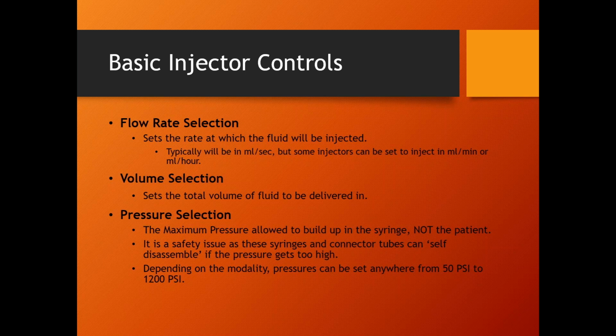CT, not as much as MRI, but CT is also a slower, longer procedure. So same exact reason. CT injections also only go up to 10 milliliters per second. So that's also why their pressure limits only go up to 300 PSI. Lower flow rates, lower pressures. So that was flow rate. I talked about volume selection, and then volume selection could be anywhere from 10 to 200. It could run the whole gamut. And then we spent time talking about the pressure limit, PSI, for pressure selection.